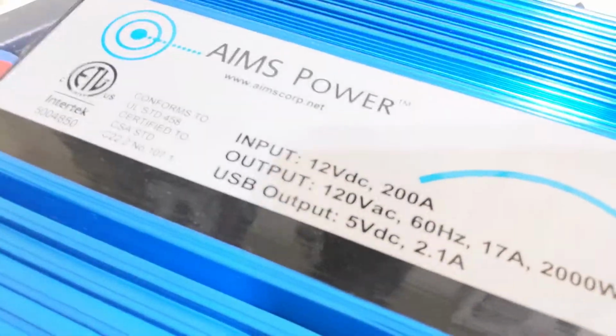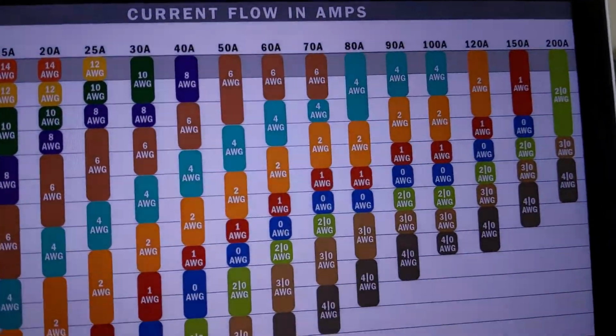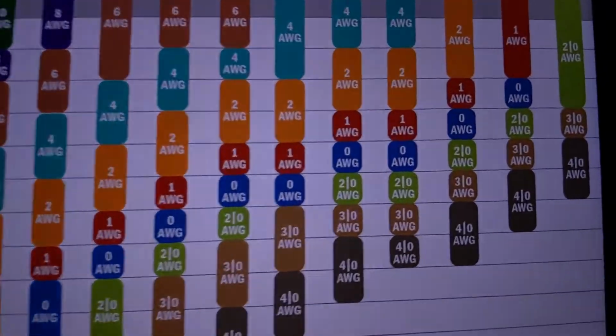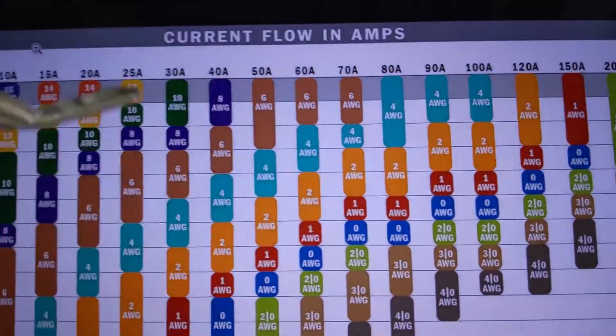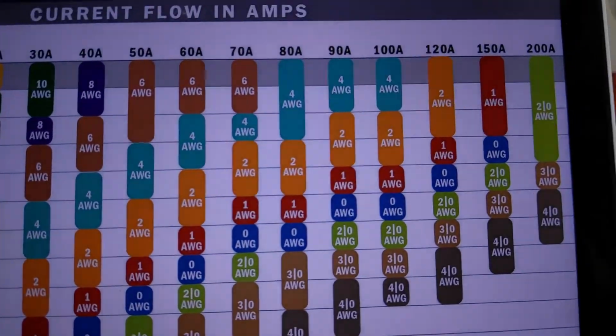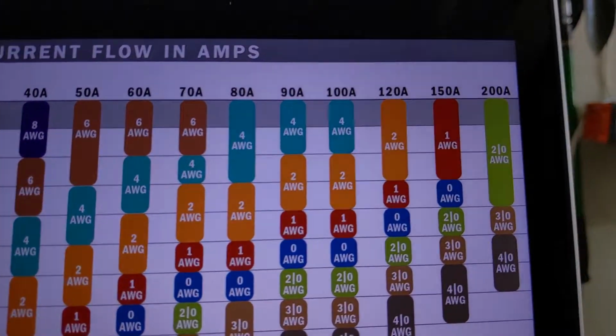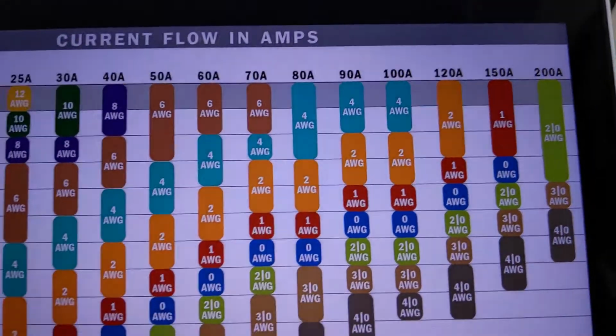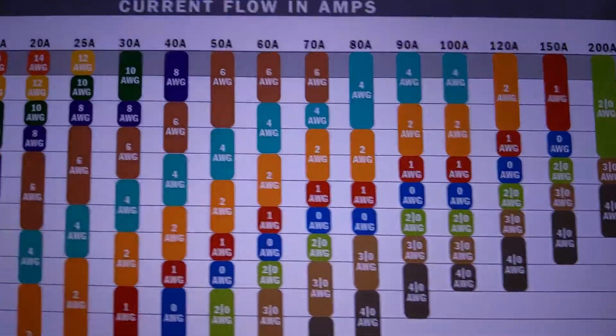So this thing can do a max of 200 amps on the input side. We're not going to get anywhere near that. We're going to use 2-gauge cables, and if we look, we can do 120 amps max off of a 2-gauge cable, which is right here.